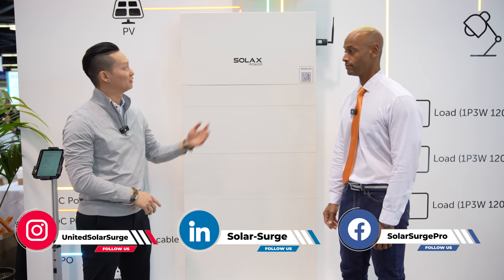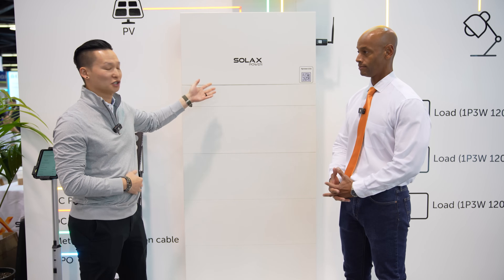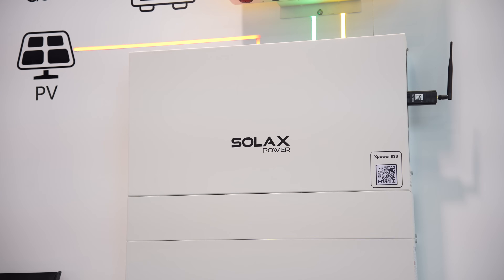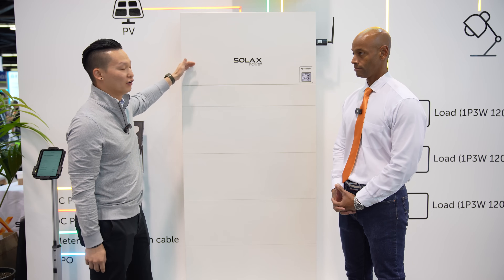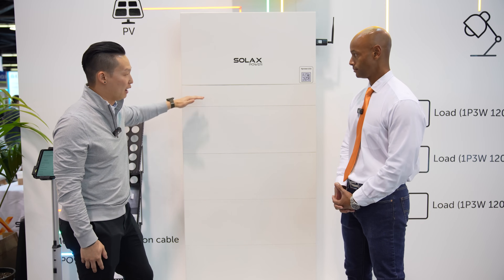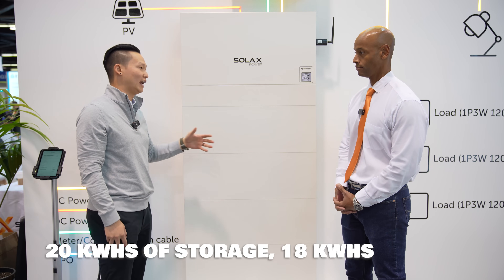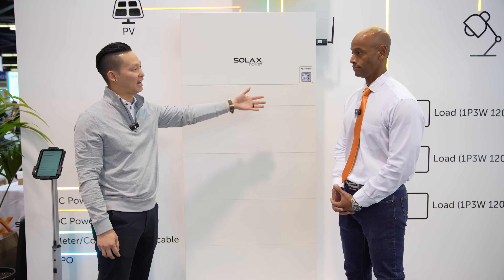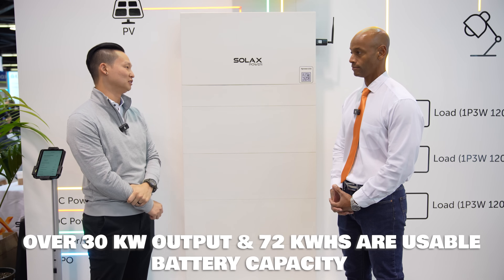Thanks, Joe. We're really excited about this product. We've been in the United States for a couple of years now. The SolaX Power is meant for modular assembly — we have multiple applications with just the one unit here. Our inverter is a 7.6 kW inverter with a BMS right here, and we can stack up to four 5 kWh batteries for 20 kWh, or 18 kWh usable. We can actually parallel four stacks for over 30 kW of output and 72 kWh of battery usable.